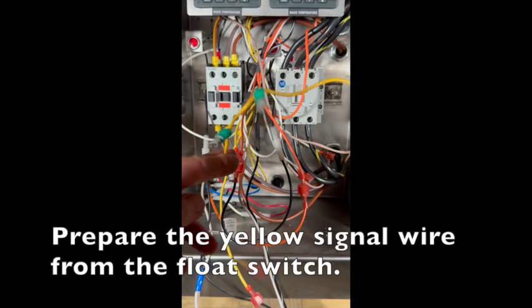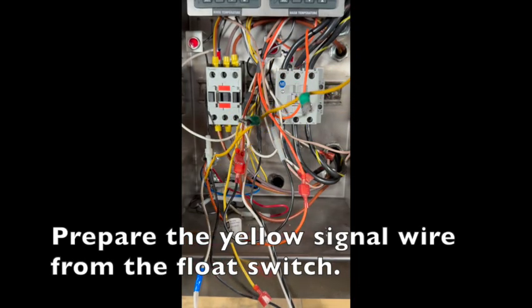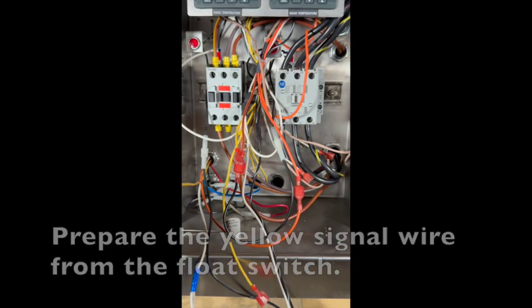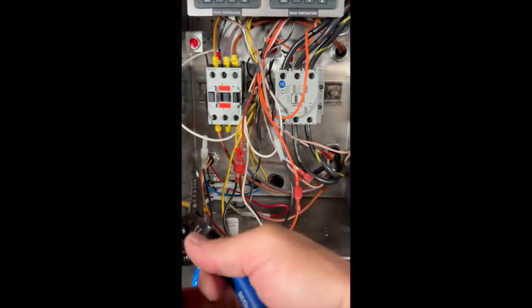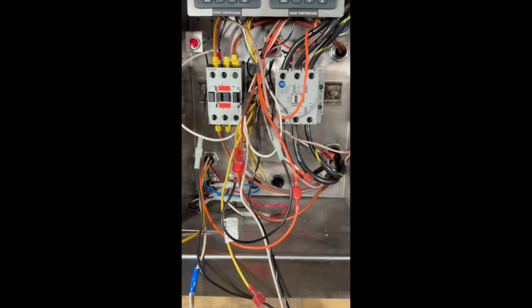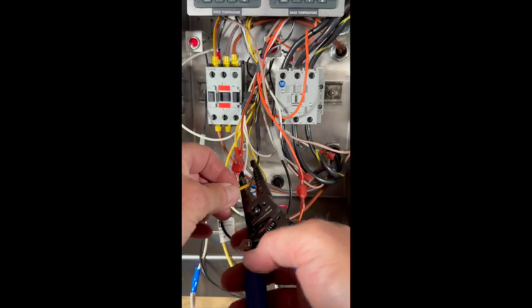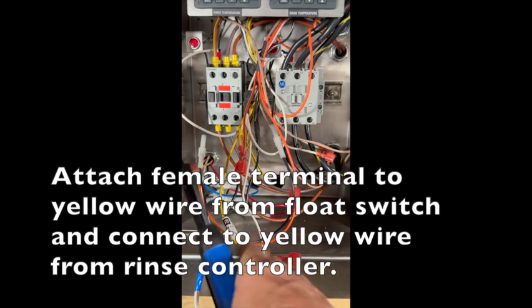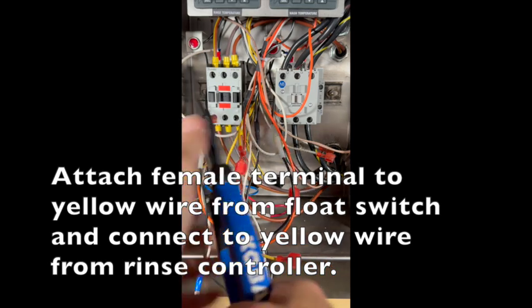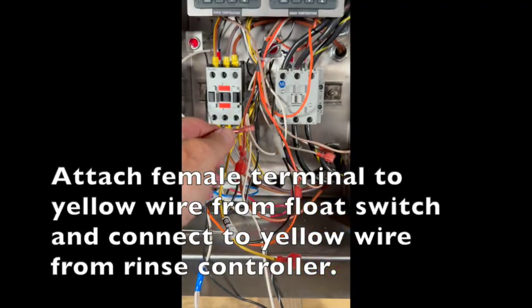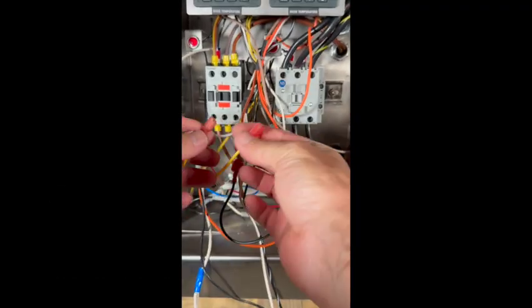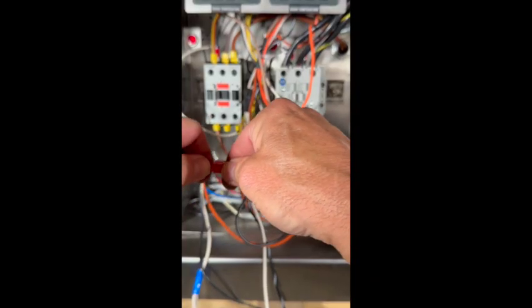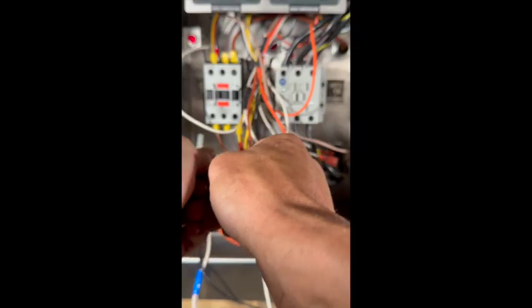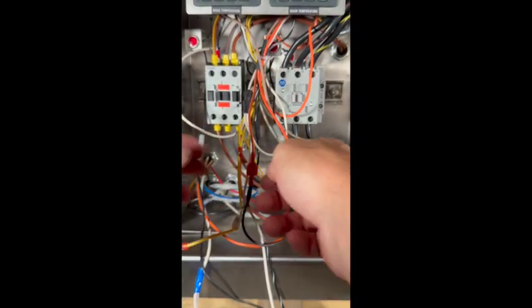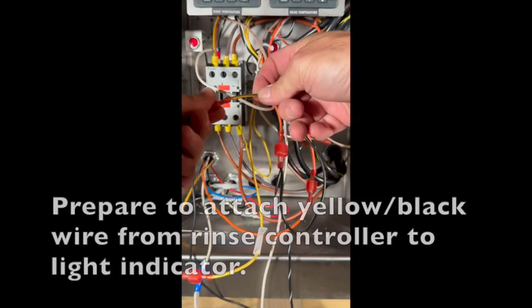Now we can prepare that yellow signal wire coming from the machine itself. We basically are going to cut off all those terminals that used to go to the delay relay. We don't need those any longer. We strip that wire, and we're going to put a female terminal on that signal wire. And that's the signal wire that's coming from the float switch of the machine itself. Now look in your wiring harness. You're going to grab the yellow wire that's got the actual male terminal already attached to it. That's coming from that controller, and we're going to put those together.